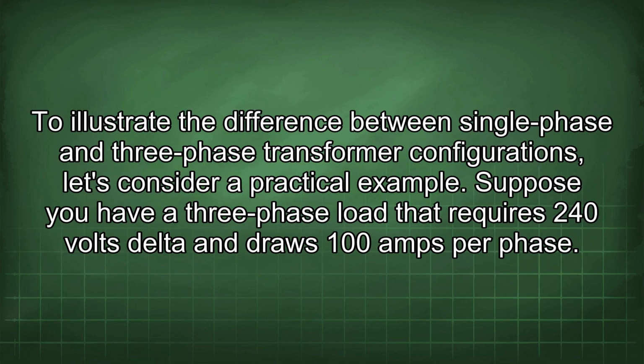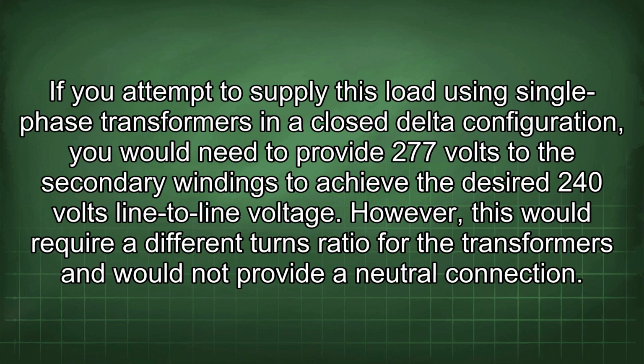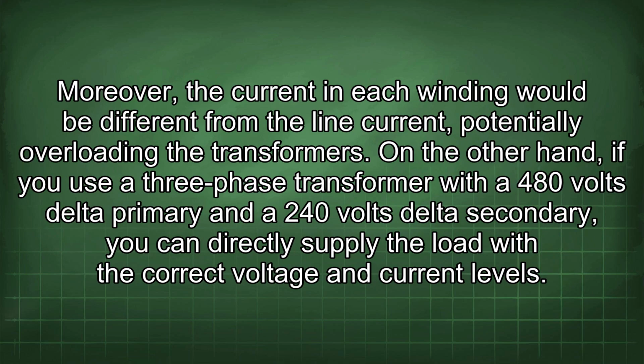To illustrate the difference between single-phase and three-phase transformer configurations, let's consider a practical example. Suppose you have a three-phase load that requires 240 volts delta and draws 100 amps per phase. If you attempt to supply this load using single-phase transformers in a closed delta configuration, you would need to provide 277 volts to the secondary windings to achieve the desired 240 volts line-to-line voltage. However, this would require a different turns ratio for the transformers and would not provide a neutral connection. Moreover, the current in each winding would be different from the line current, potentially overloading the transformers.